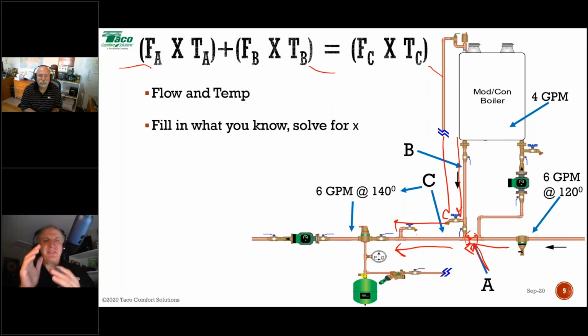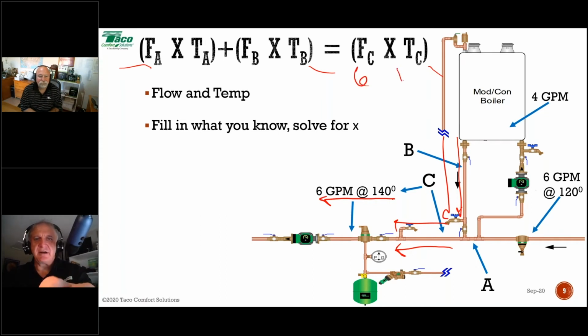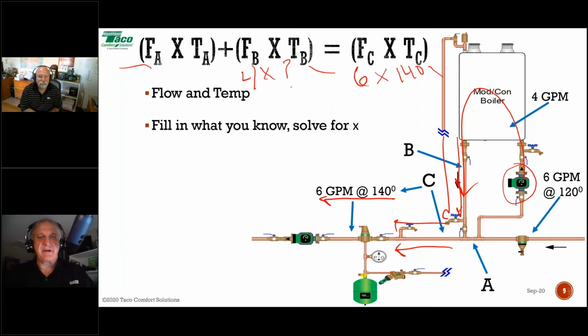So if we think about this, we know 5 of the 6 variables already. Let's take a look here, okay? In this example, my flow for the system is 6 gallons per minute at 140. Well, that's C, right? So 6 times 140. B is the boiler, and that's 4 gallons a minute. This circulator and the boiler requires a flow rate of 4 gallons a minute through that heat exchanger. So I know the flow there is 4 gallons a minute times we don't know. The temperature is what we got to find out.